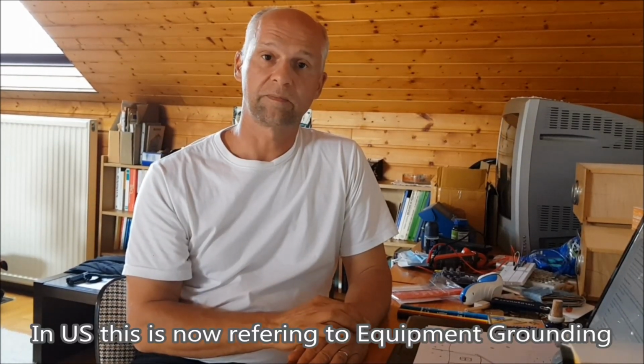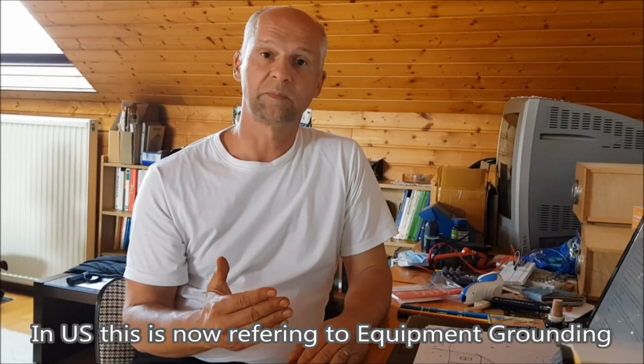But why does Northern America not use central RCDs like the rest of the world? This, you will see in a moment, has something to do with the lower system voltage. And to explain this a little bit better, we will take a look generally into electrical circuits and how the protective earth system, so the PE system as a raw system without any technical device, is working, and what voltage actually has to do with that as well.